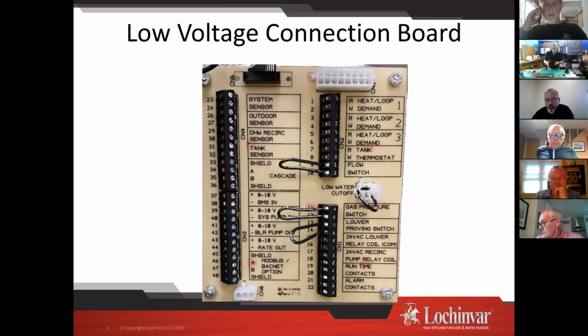And if you do look at the board itself, just from a troubleshooting perspective, the right-hand side of the board, that's all 24-volt terminals. The left-hand side of the board, we're getting into DC terminals and resistance terminals. Our sensors are based on resistance. We do have some DC input and output terminals on that other side as well. So just know which side of the board that you're on. If you're not certain, the 24-volt side actually does have 2 items on there that are labeled 24-volt, and that'll give you the clue as to what side of the board you're on.